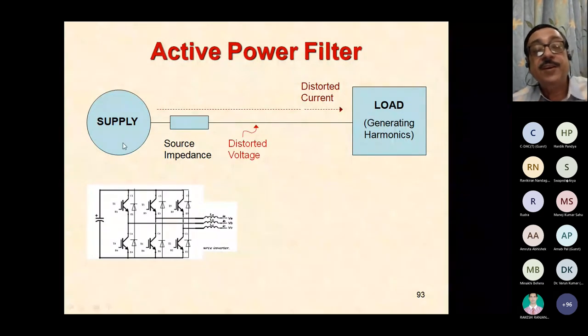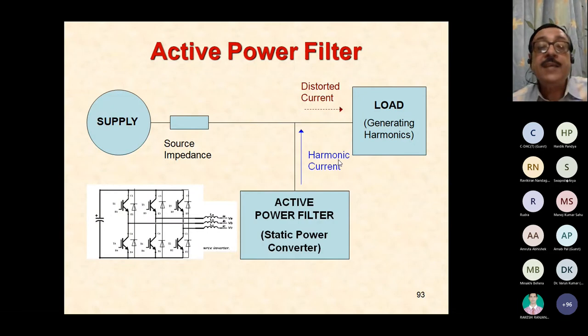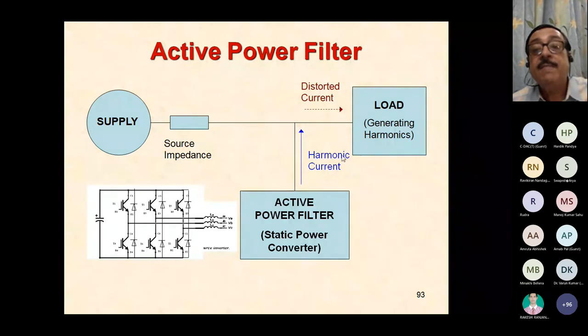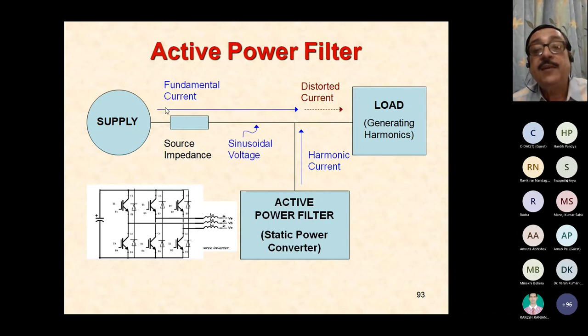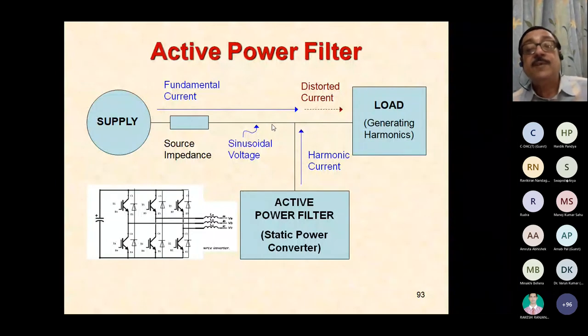Suppose this is a supply generating source with the source impedance, and this is my load which was generating harmonics, so I was drawing a distorted current and therefore resulted in a distorted voltage at this bus. Now I inject harmonic current into this point through a so-called active power filter, which is nothing but the same bidirectional converter with a capacitor connected to the grid, where I monitor what is the current flowing through in this bus, and I duplicate the same current here with a 180 degree phase shift, such that the current drawn by this load is actually supplied from here, so that the resulting current disappears from this bus. So here it becomes fundamental current only, and therefore it goes back to a sinusoidal voltage, because harmonics are not there, so harmonic drops disappear. They become a sinusoidal voltage once again. So all its harmonic current is supplied by the so-called active power filter.